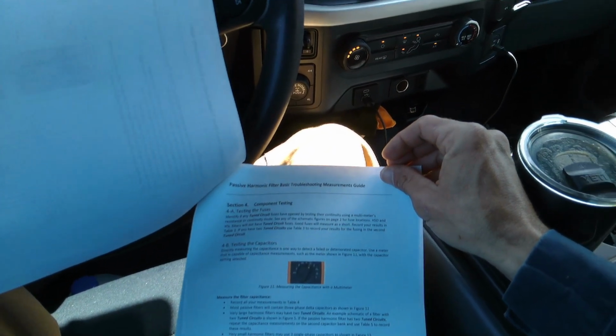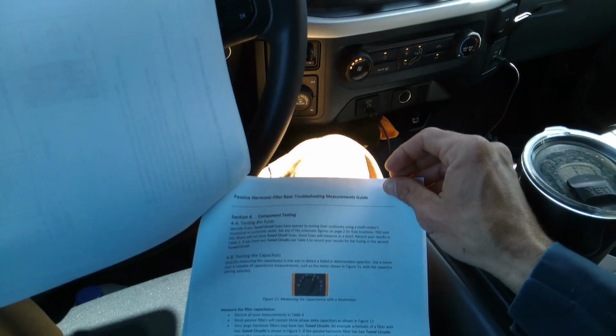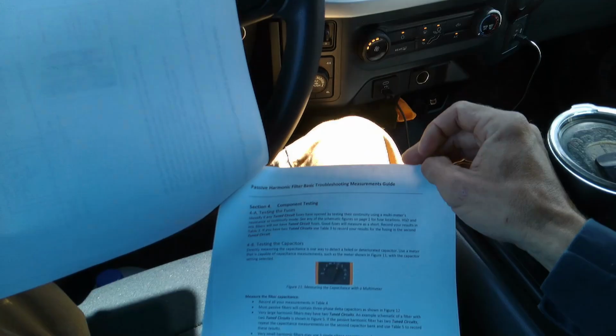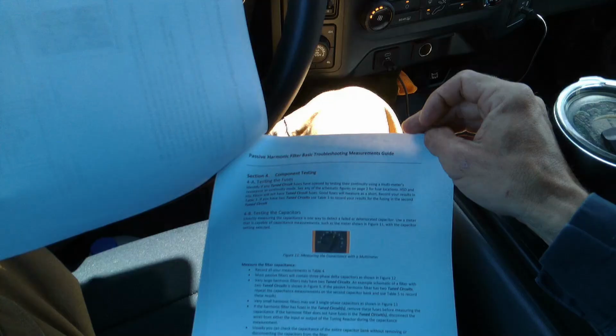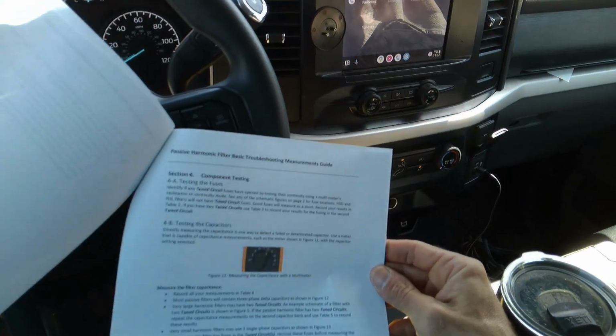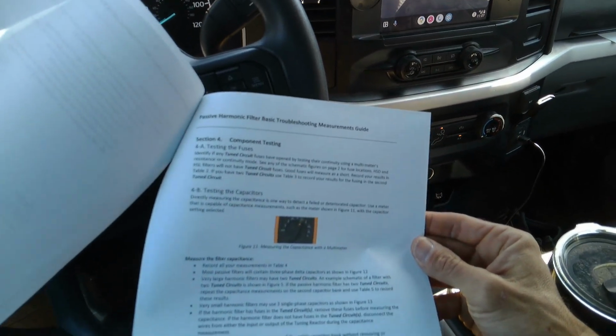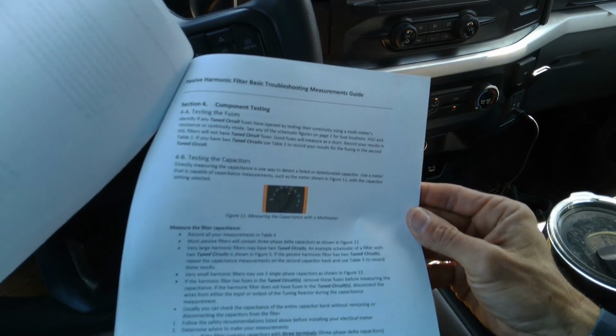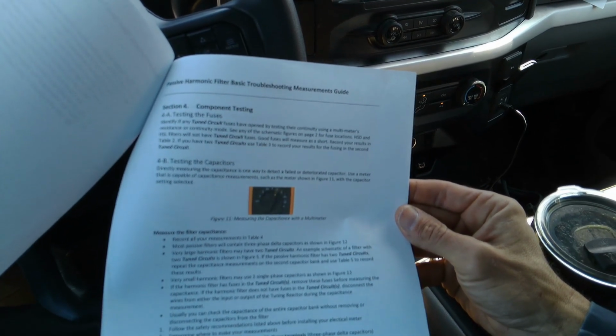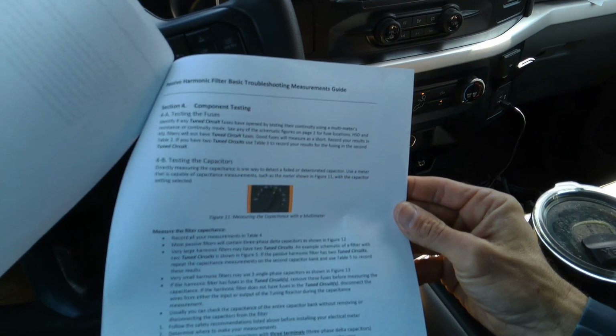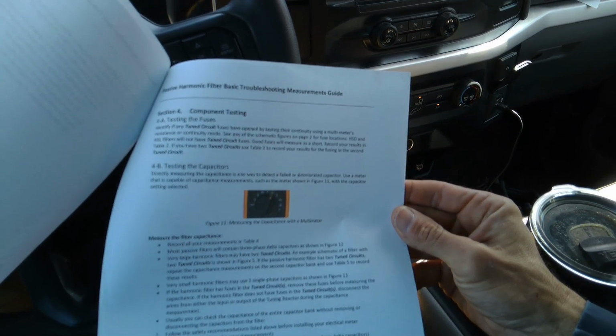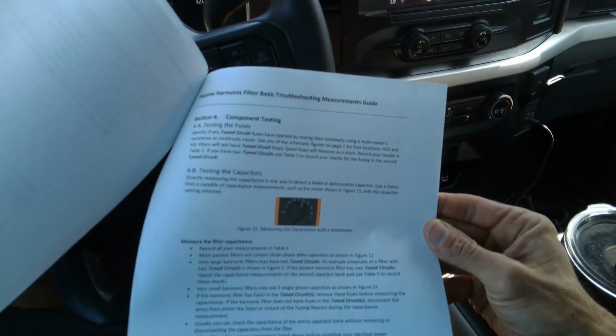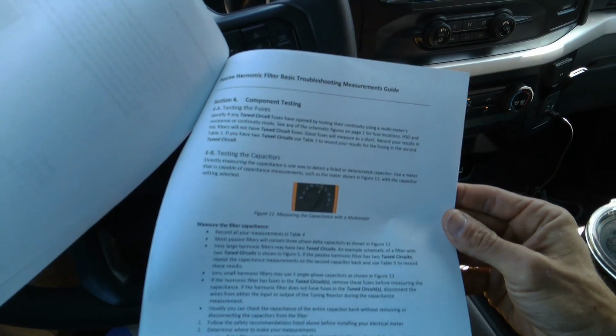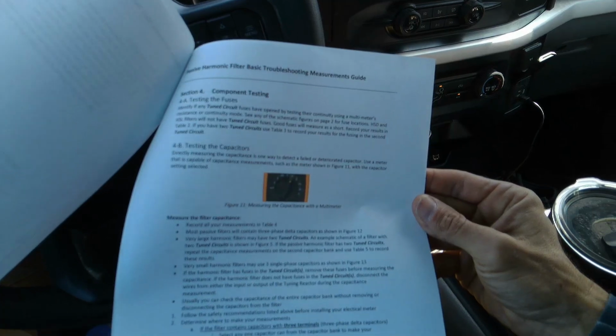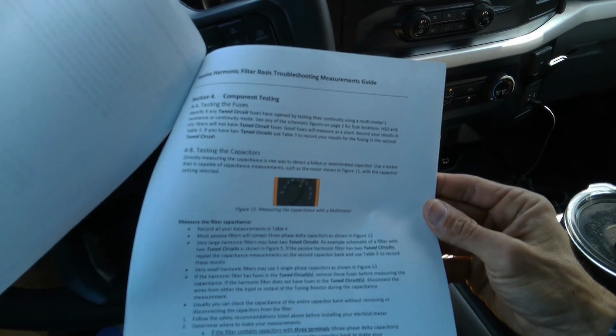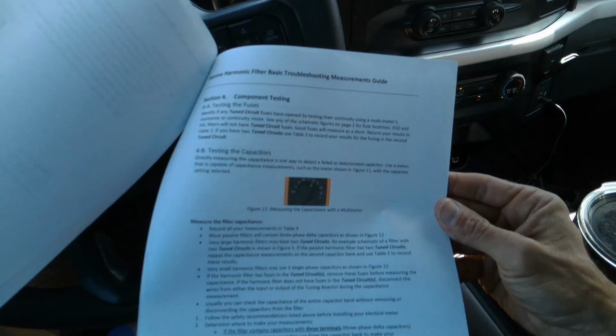Usually you can check the capacitance of the entire capacitor bank without removing or disconnecting capacitors from the filter. Determine where to make your measurements. If the filter contains capacitors with three terminals, three-phase delta capacitors, select any one capacitor from the bank to make your measurements on. You will only need to make your measurements on this single capacitor because all the capacitors will be wired up in parallel and all their capacitances will add together. Assign arbitrarily a letter A, B, and C to each of the three terminals on this capacitor. You'll be measuring between these terminals.